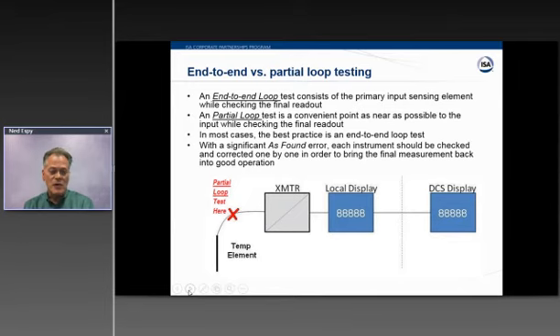Maybe you can have an extra thermal well or have a way to insert a thermometer temporarily into the process to make a comparative measurement and just verify that the element's in good shape as well. So those are the two types of ways you can try to test using a loop approach. And even though you're not checking the transmitter and the local display, as long as the end-to-end result is accurate, there's really no point in checking it.